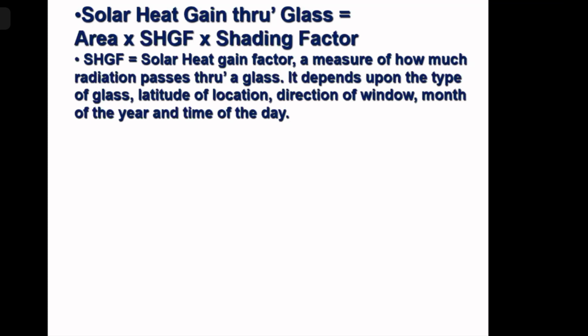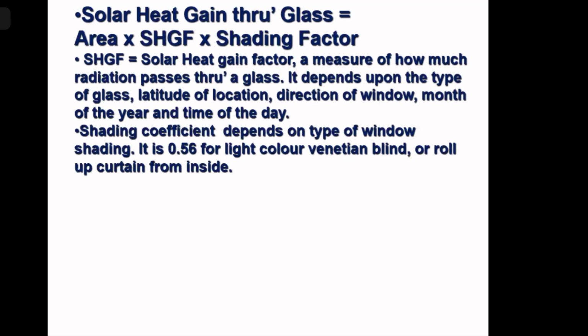In our air conditioning calculation for Calcutta, we consider normal glass, latitude is 22 degree latitude. So we consider 22 degree latitude for Calcutta. And direction of window, for each window we calculate. North, south, east, west, every direction we take window, and for that we have different solar heat gain factor. And month of the year, we consider the hottest month of the year. In Calcutta, we consider June to be the hottest month of the year. Next. It depends on the type of curtain we are giving. It is 0.56 for light color Venetian blind or roll up curtain from inside. Next.